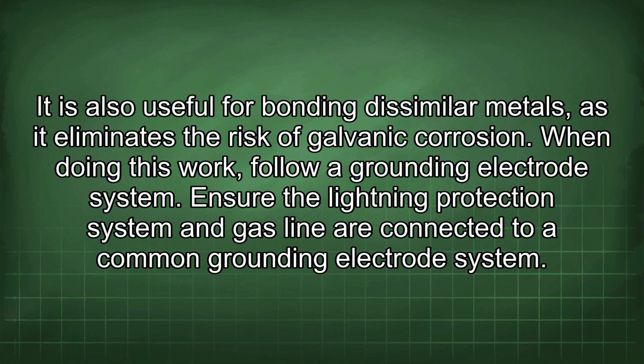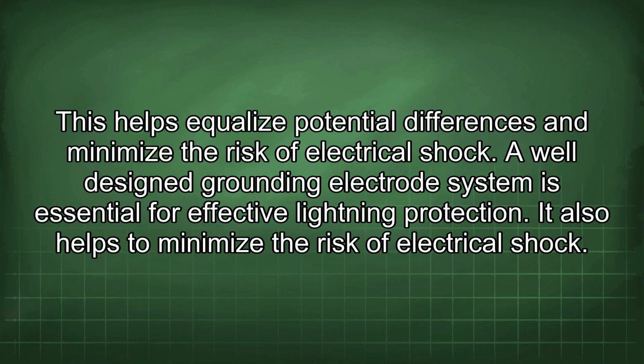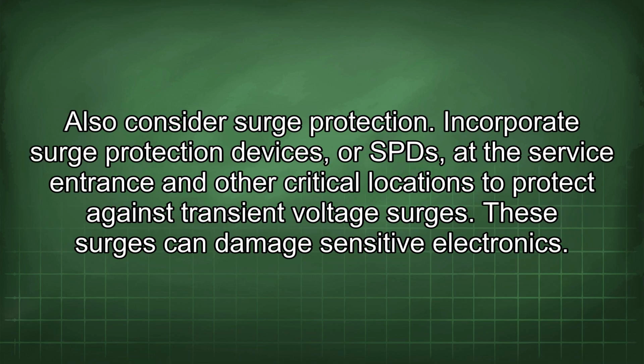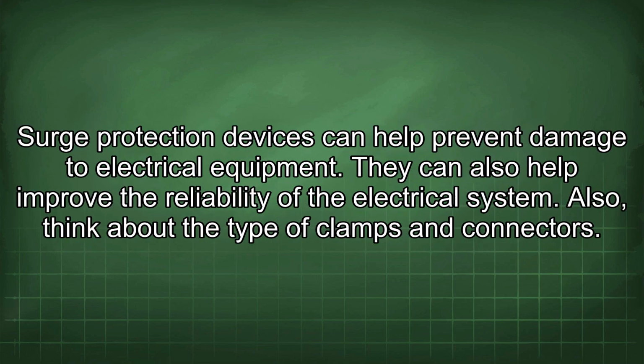When doing this work, follow a grounding electrode system. Ensure the lightning protection system and gas line are connected to a common grounding electrode system. This helps equalize potential differences and minimize the risk of electrical shock. A well-designed grounding electrode system is essential for effective lightning protection. It also helps to minimize the risk of electrical shock. Also consider surge protection. Incorporate surge protection devices, or SPDs, at the service entrance and other critical locations to protect against transient voltage surges. These surges can damage sensitive electronics. Surge protection devices can help prevent damage to electrical equipment. They can also help improve the reliability of the electrical system.